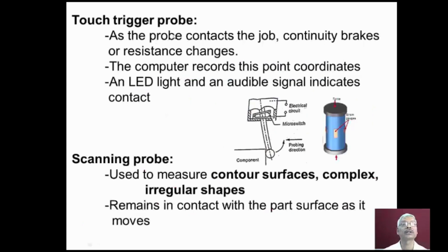Now in the case of the touch trigger probe, as the probe contacts the job as shown here, the continuity breaks or resistance changes. If it is a probe with micro switch type, the micro switch gets opened and a signal is sent to the CMM software. If it is a probe based on strain gauges, when the probe deflects, the resistance of the strain gauge changes, and hence a signal is sent to the software. The computer records this point's coordinates. That means whenever the probe comes in contact with the component, that particular point's coordinates are stored by the computer. An LED light and an audible signal indicate the contact.